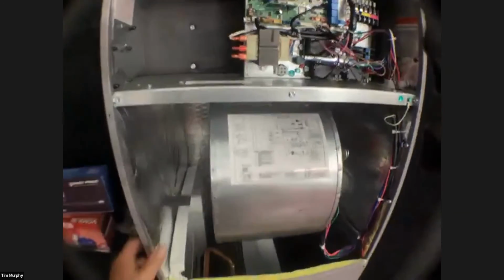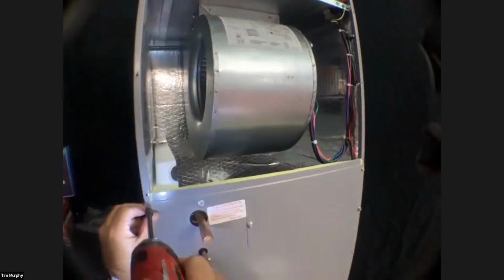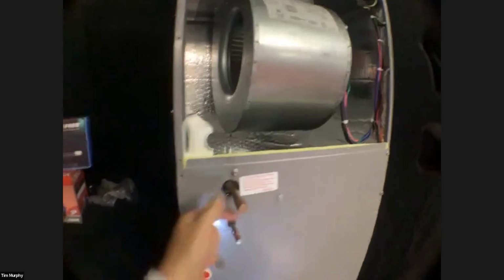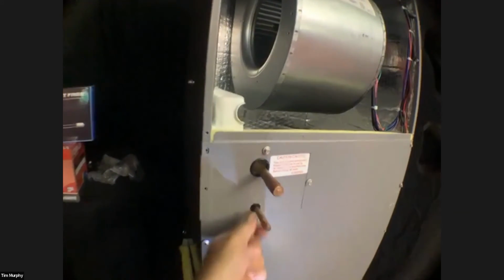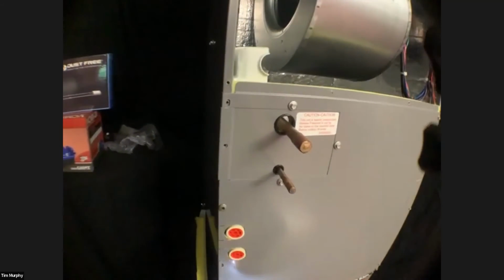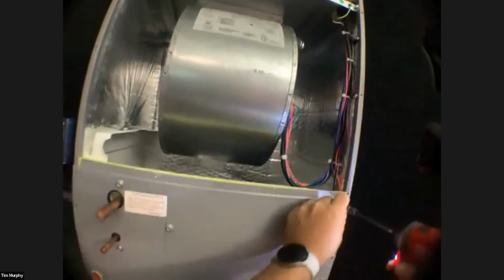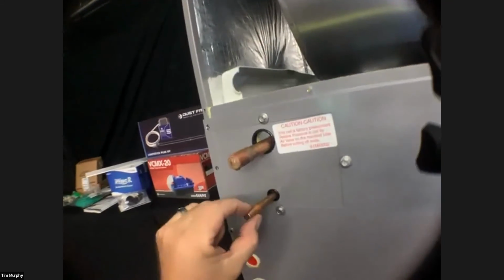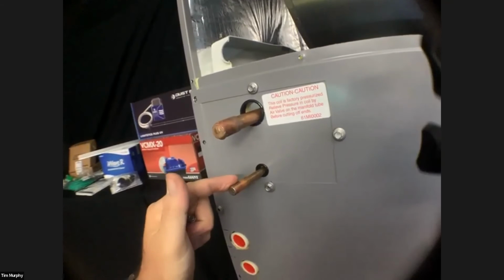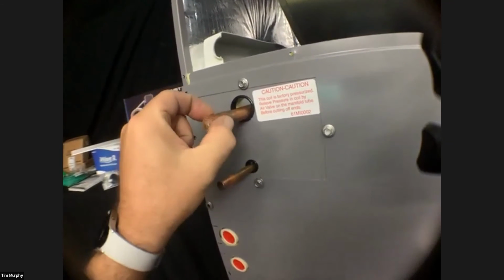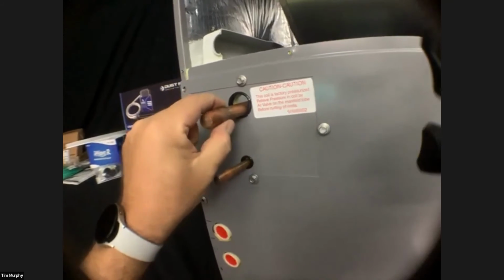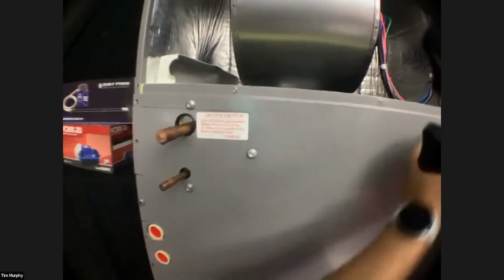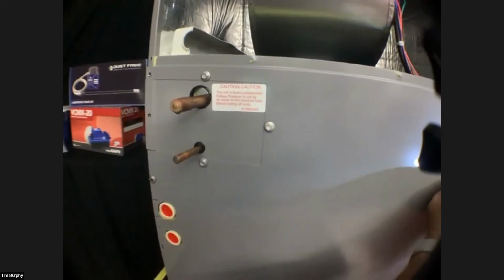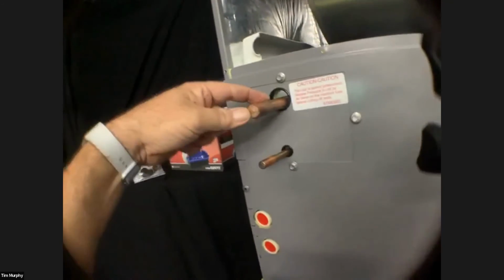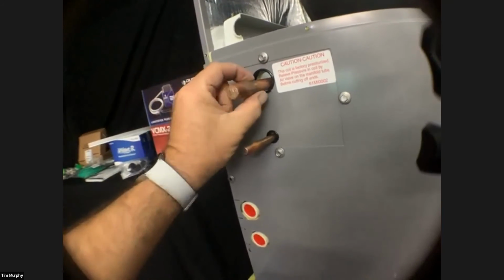So now we're going to work our way down to the coil. As you can see, that's your copper fitting, your copper connections for the evaporator coil. And by all means, they are flared. So if you're going to braze, you can just cut these ends off, and then, this is 5/8 and 3/8, you'll be able to slide your copper in there. If you're going to utilize the Zoomlocks, with the 5/8 you're going to have to cut these bell ends off and then attach the Zoomlocks here and here.